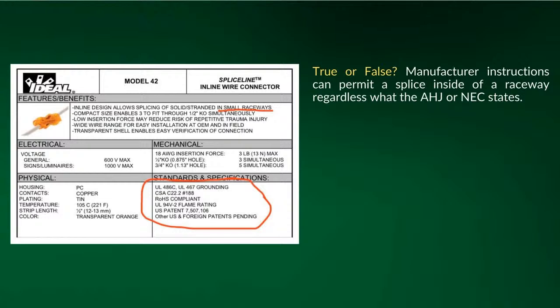But it was pretty awesome that we were able to pick this up from this individual and run it for the myth of the week, because it was a valid point. Now, what I would argue, and I've done this before with inspectors, is I've actually gone and looked up that UL number. If you have something from the manufacturer that says this is listed and labeled to be installed inside a wet location conduit, I could see the argument. The problem is the inspector is going to say those splices have to be accessible, and if you have to remove 12 inches of dirt to access that splice, that's not going to be compliant. So it was pretty awesome we were able to run this this week.